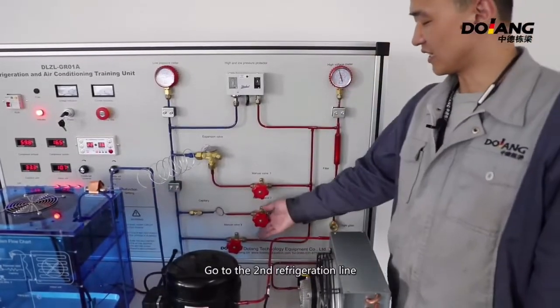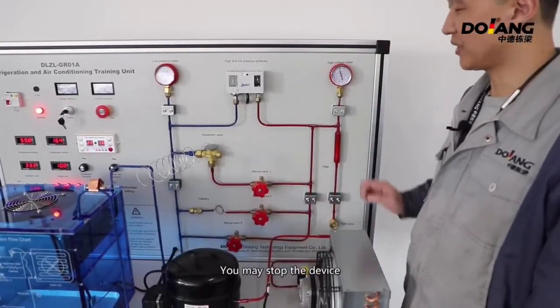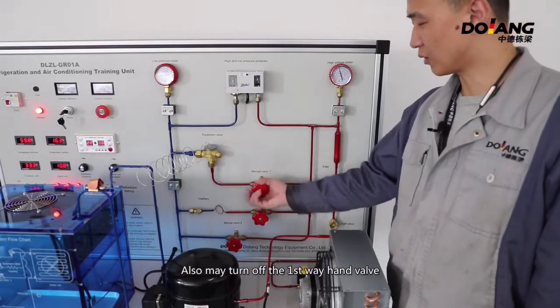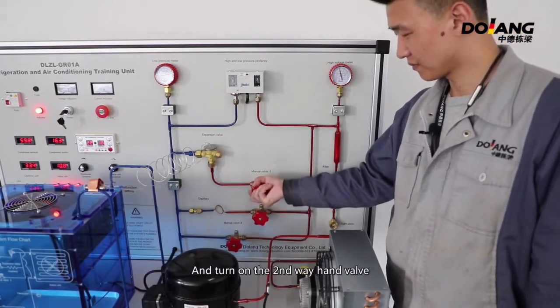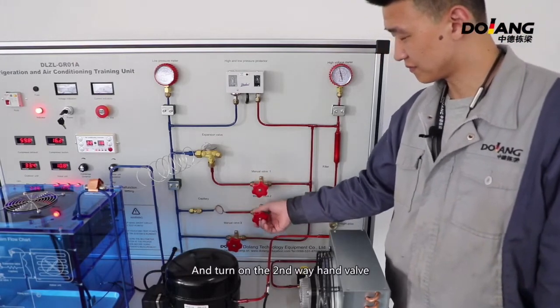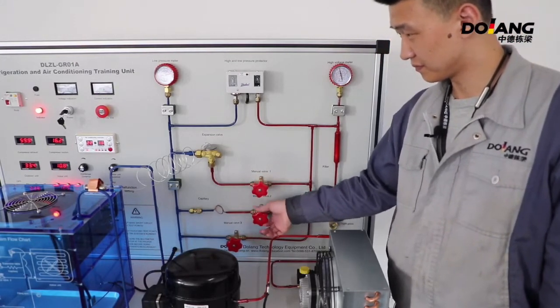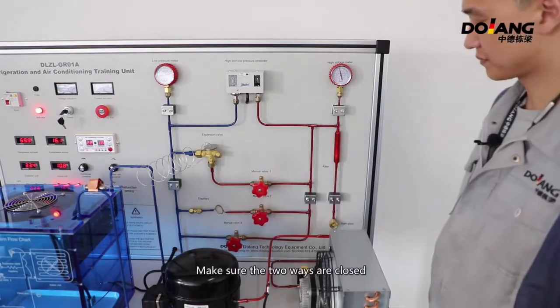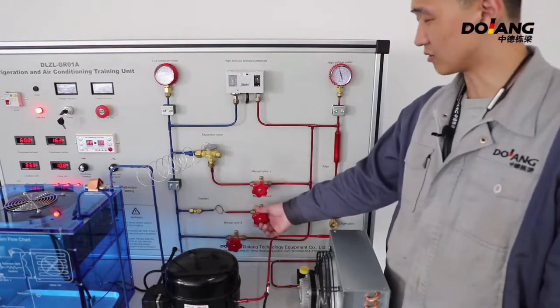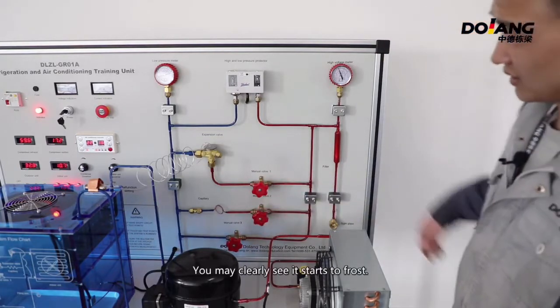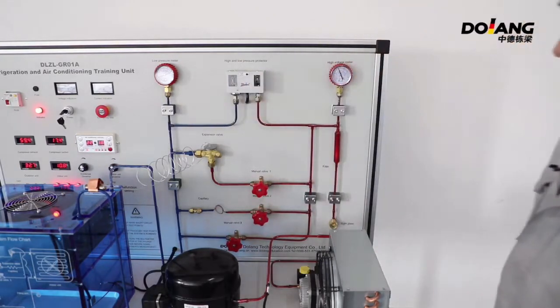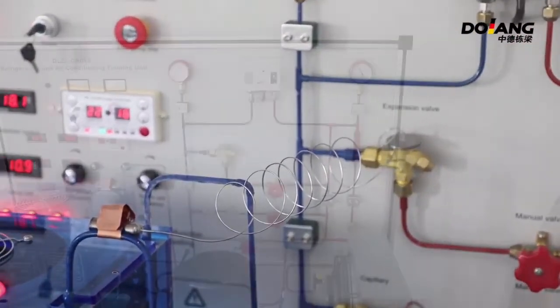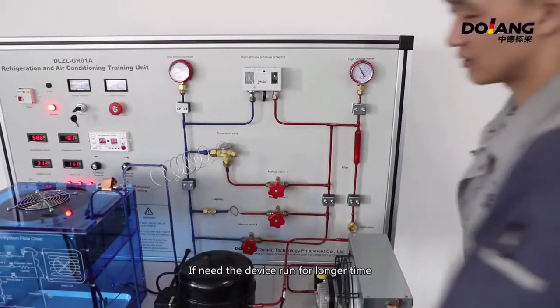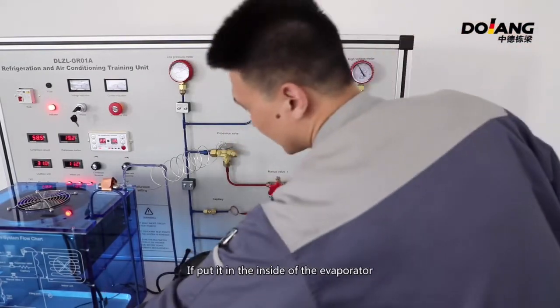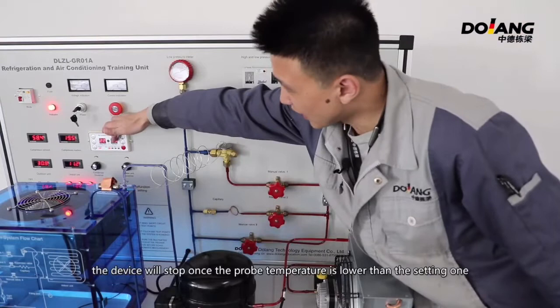Go to the second refrigeration line. You may stop the device. Also turn off the first way hand valve and turn on the second way hand valve. Make sure the 2 ways are closed. You may clearly see it starts to freeze. If you need the device to run for a longer time, you may take out the probe. If you put it inside the evaporator, the device will stop once the probe temperature is lower than the setting one.